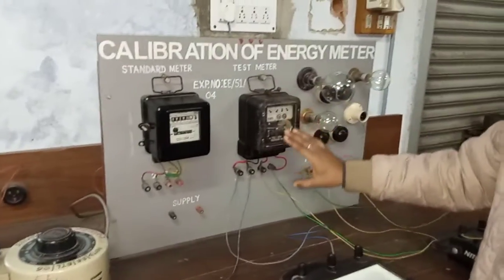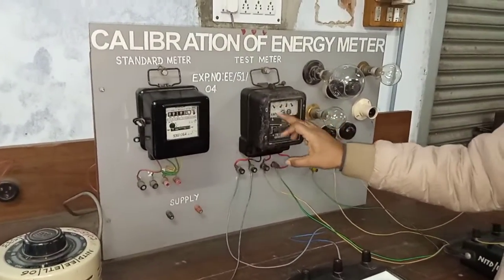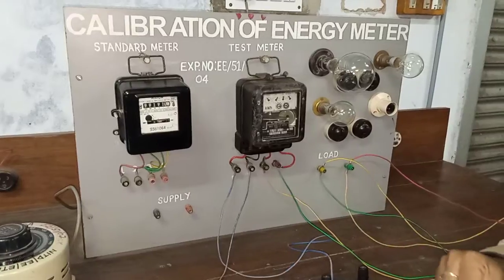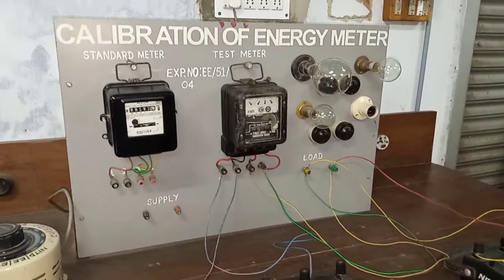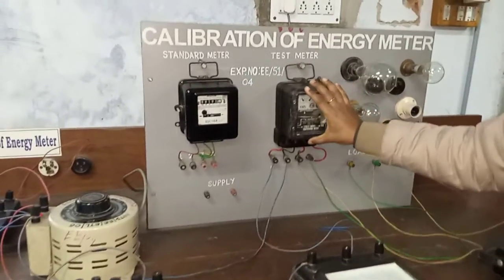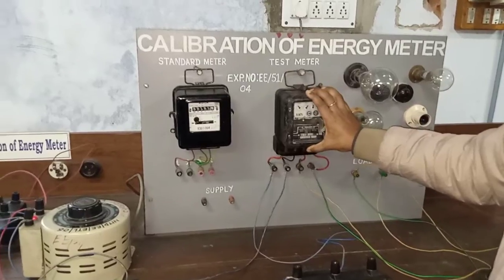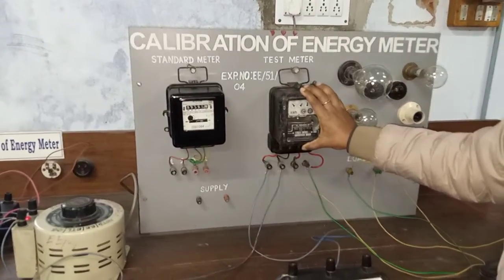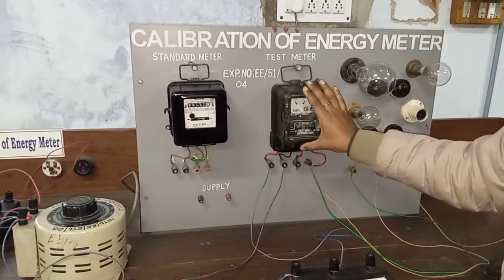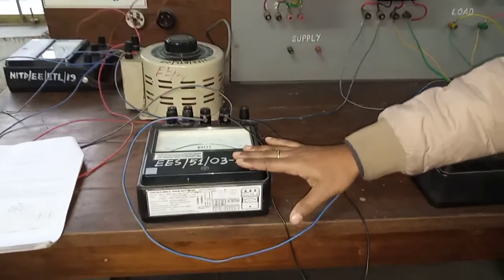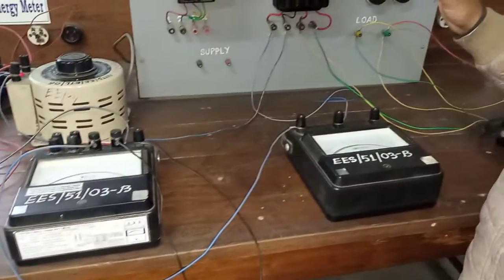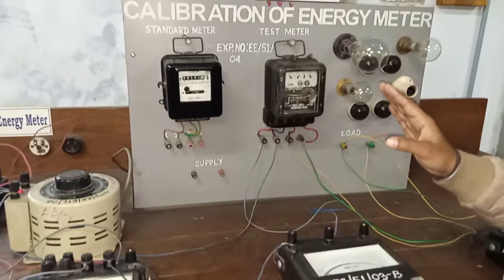After 10 minutes, we will find the final reading of the energy meter, and from that we will find out how much energy this energy meter has registered. So this reading will be the test reading, this will be the standard reading, and accordingly we will do that.